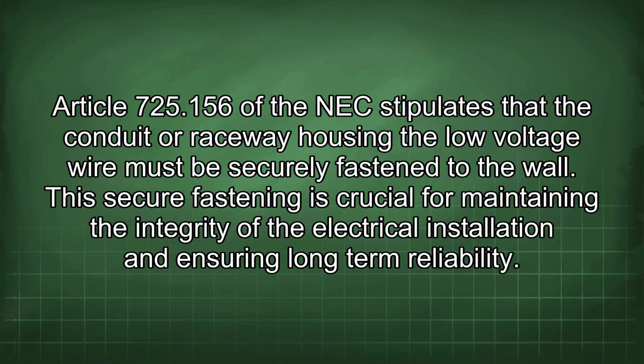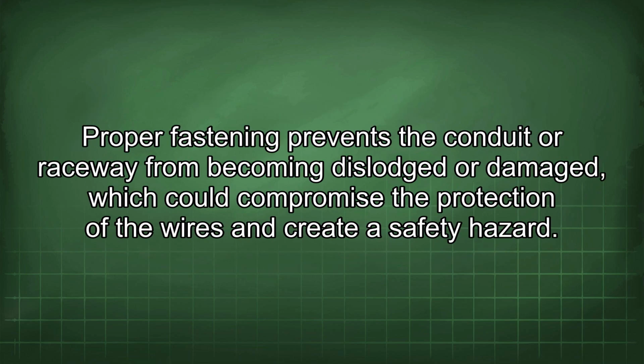725.156 of the NEC stipulates that the conduit or raceway housing the low-voltage wire must be securely fastened to the wall. This secure fastening is crucial for maintaining the integrity of the electrical installation and ensuring long-term reliability. Proper fastening prevents the conduit or raceway from becoming dislodged or damaged, which could compromise the protection of the wires and create a safety hazard.